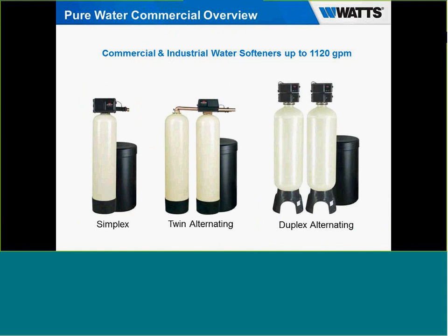We have a full line of commercial softeners, starting out with our standard Simplex systems, which would be this single tank system here, and these are offered in a 1-inch up to 3-inch configuration. We have our twin alternating, and this system here is designed to give you 24/7 softened water. Typically, a water softener regenerates like 2 a.m. in the morning when water's not being used, but with our twin alternating, you notice it has two mineral tanks here and one brine tank, and it only has one control valve.